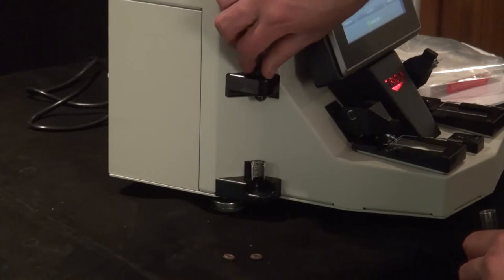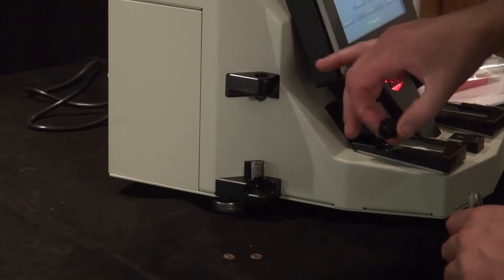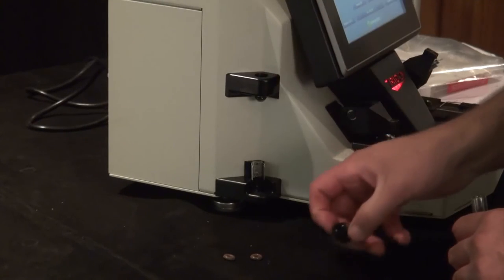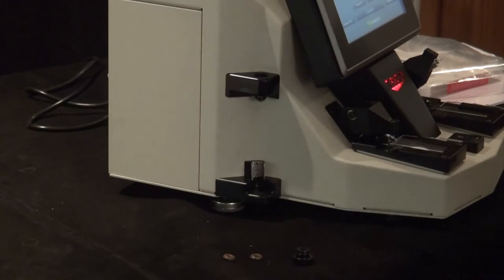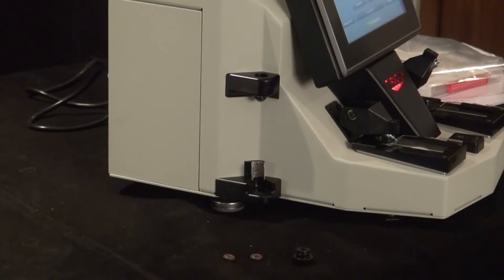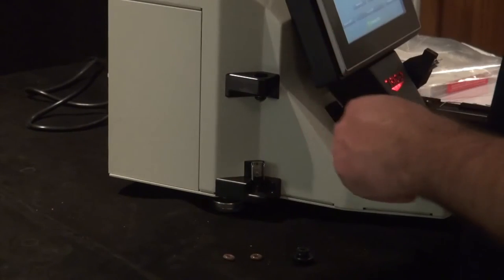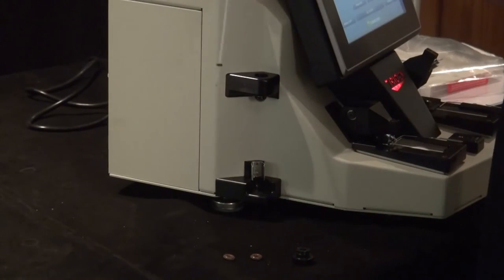For the top o-ring, if you take the cap off, it just unscrews. There is a tiny o-ring on the inside. To replace that, just take your sample tube and put it through the o-ring and pop it out. Now it's on the sample tube.